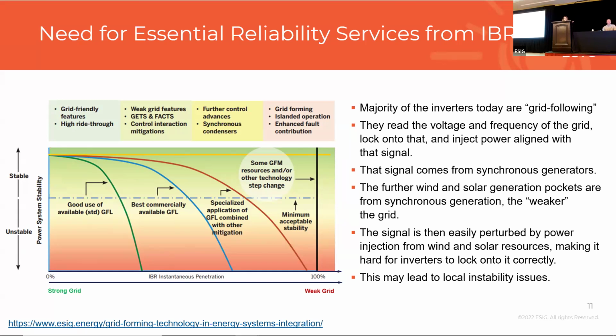As we started integrating inverter-based resources, we progressively went from just needing to generate megawatts, to now needing to provide services to the grid. The first service asked for was that the resource is grid friendly and rides through faults, so whenever faults happen on the grid, inverter-based resources don't just trip offline and exacerbate the fault. As we progressed further and weak grid became an issue, there was an ask for weak grid features, more stable controls in weak grids, and control interaction mitigations people started to look for.